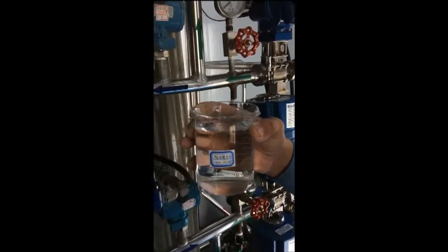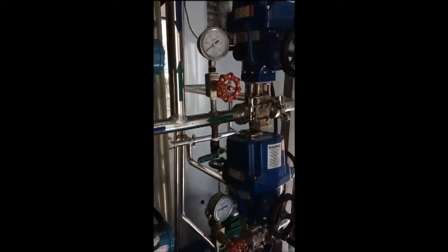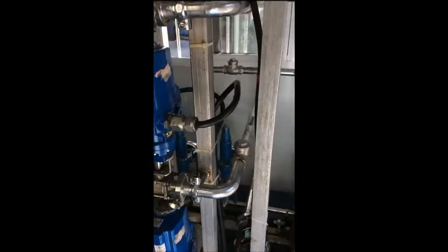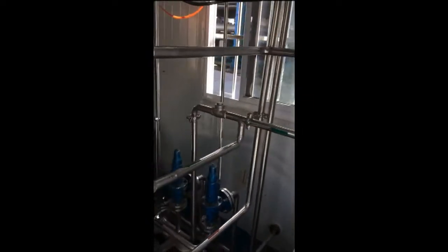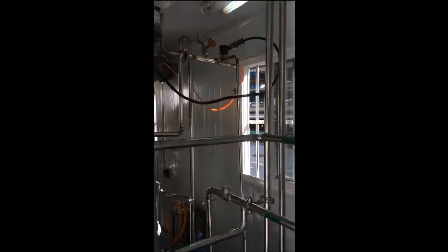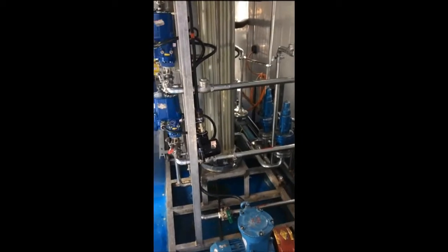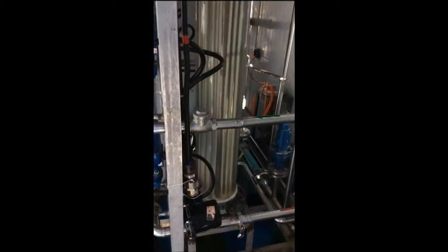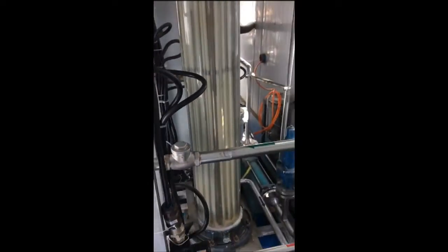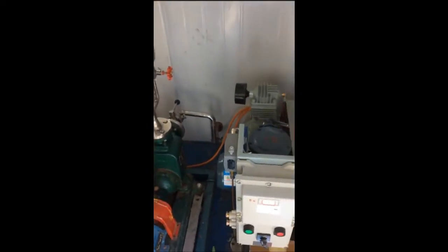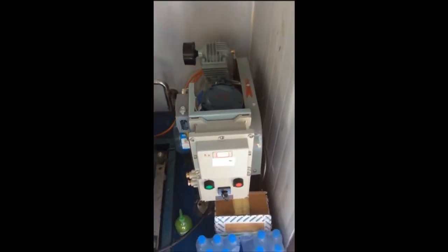This is, by the way, a sample of the water after the membrane, and the turbidity of the water going into the membrane was about 4 NTU, and coming out of the membranes was less than 0.2 NTU. But the membranes themselves, these are the tubes, and as I said, we add a powder to that tube that creates the skin layer. It improves the flux rate dramatically and reduces the pressure requirements dramatically.